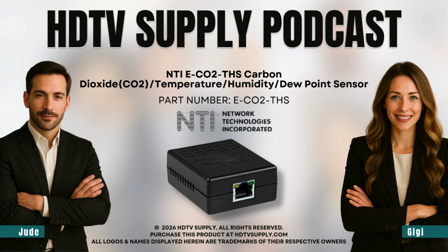So that brings up a question. We're talking about a server room. Servers don't breathe, so why do we even care about CO2 levels in a data center? That's a super common question, and you're right, the servers themselves don't care. But the CO2 level is a fantastic proxy for two other things: human presence, and more importantly, HVAC efficiency. So if the CO2 is spiking, it means your air exchange is sluggish, you're getting stagnant air, and stagnant air leads directly to heat pockets. And a heat pocket will absolutely kill a server drive. So it's less about breathing and more about validating your airflow, an efficiency metric.